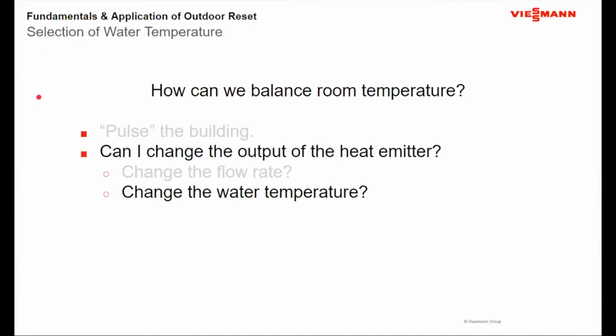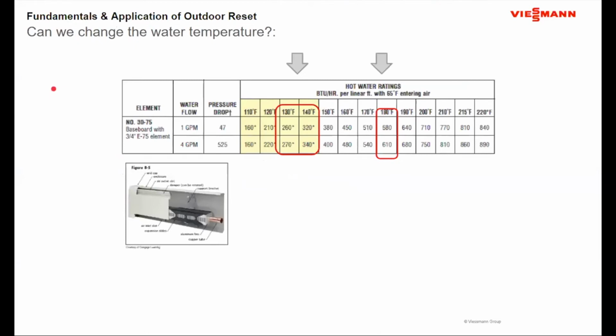So the final option, and the option we're really here to talk about today, is changing the water temperature, which becomes the most viable option when we're trying to balance room temperature. Okay. So from the aspect of heat emitters, coming back to my baseboard, at 180 degree water temperature, I can get about 600 BTUs per linear foot. If I drop my water temperature down to 135 degrees, I get about 300 BTUs per linear foot. Now, when you start to look at responses, and I compare the water temperature to the room temperature, the relationship between a 65 degree room and a 180 degree baseboard, at 135, it's about half the difference.